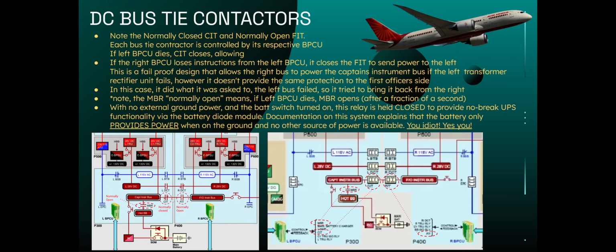Why? So that no matter what happens, if something fails, the left bus is kept up at any cost. So let's say we lose the left BPCU. This would close, because it would see that's off and would connect. It's normally open, but if powered, it's keeping it closed, which would push power through and bring that back from the dead. That would have happened for a split second until the short circuit pushed its way through and then turned this off until the main battery relay opened.